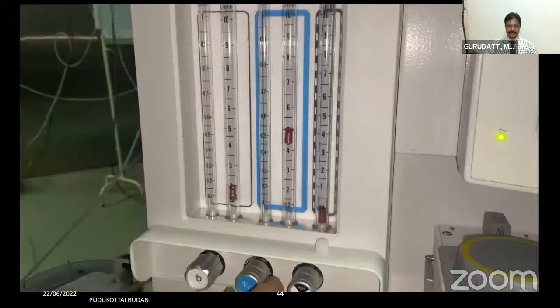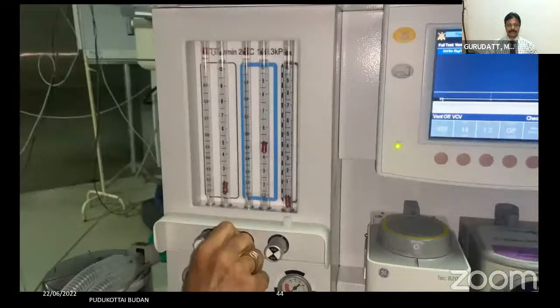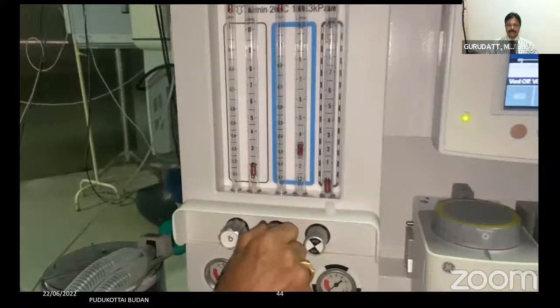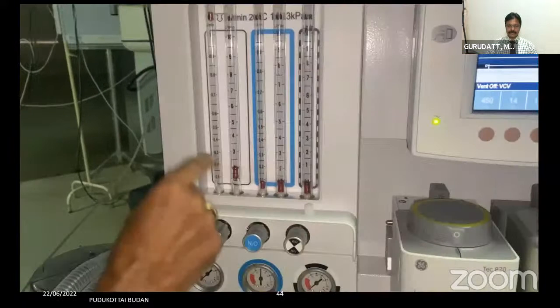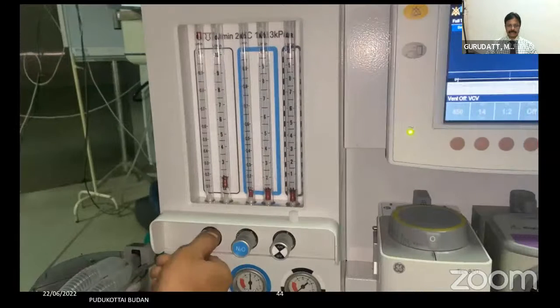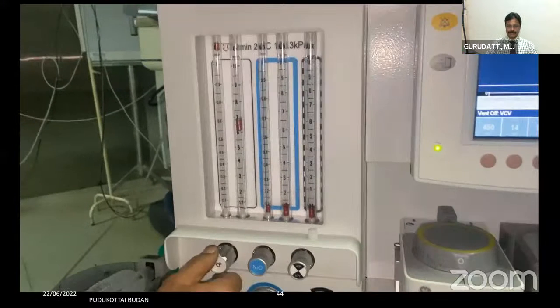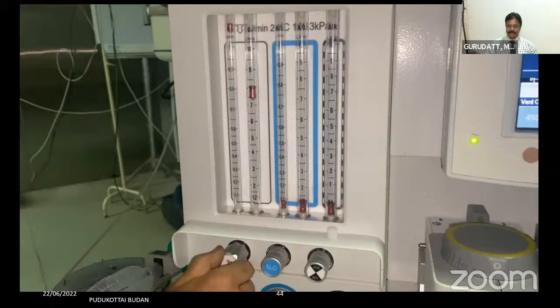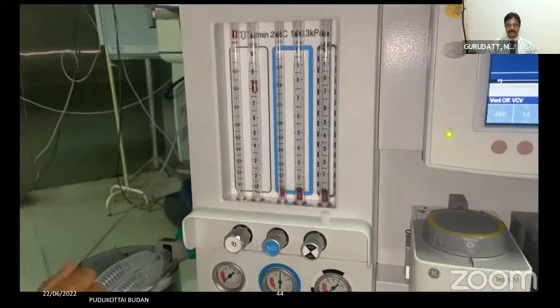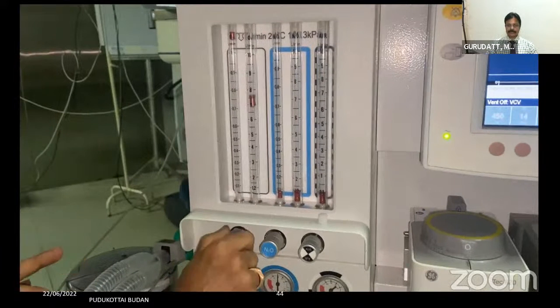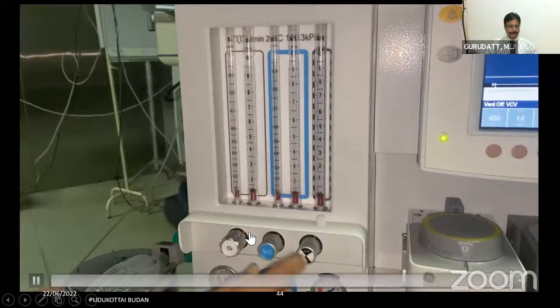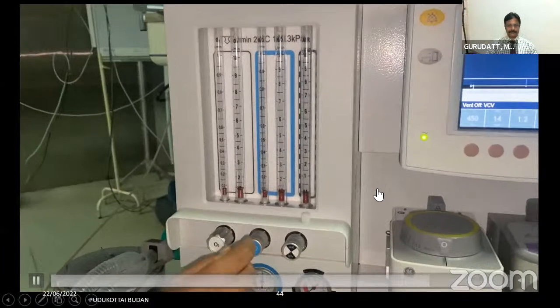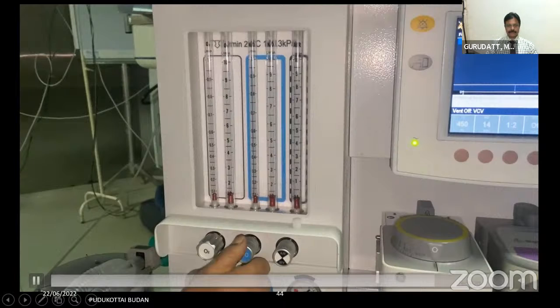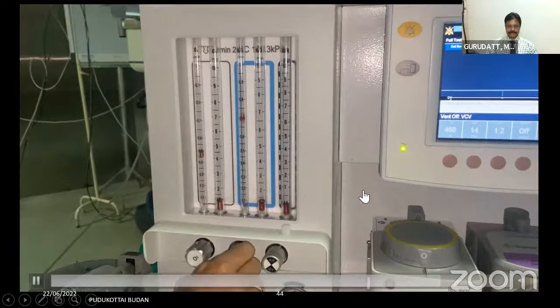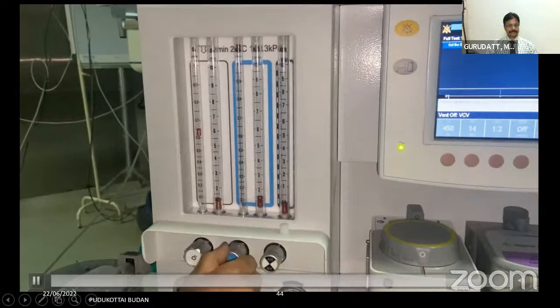Now if I close the nitrous oxide alone, oxygen will remain like that, and I can also give only oxygen. When I am giving only oxygen, the nitrous oxide flow control knob will not rotate. So this is the Link-25. Again, in order to know whether it is Link-25 or ORMC, just rotate the nitrous oxide knob. If oxygen rotates, it is Link-25.